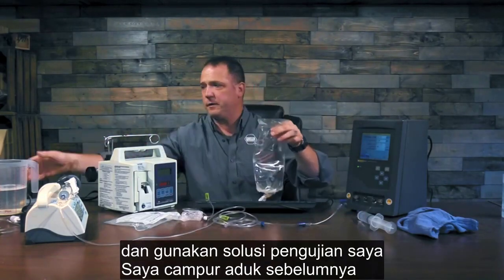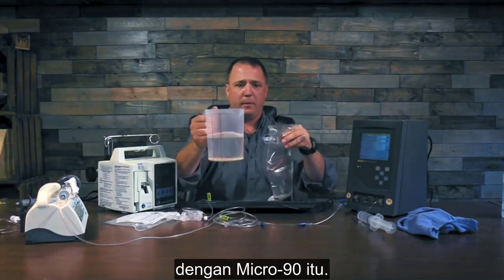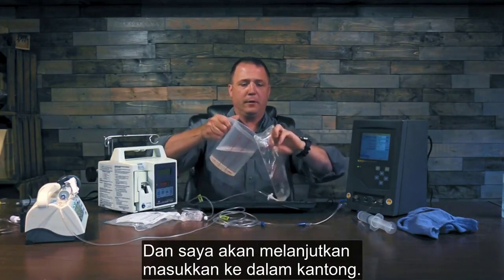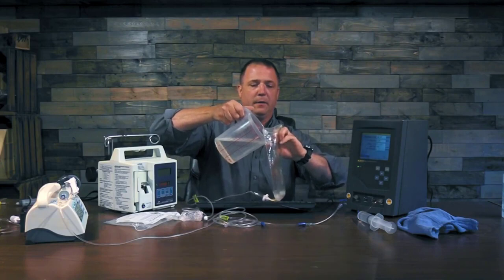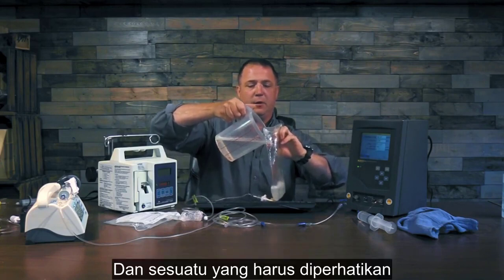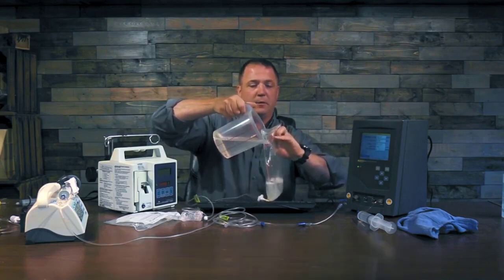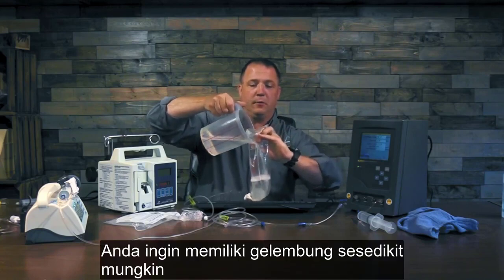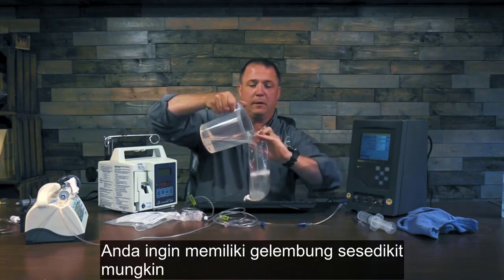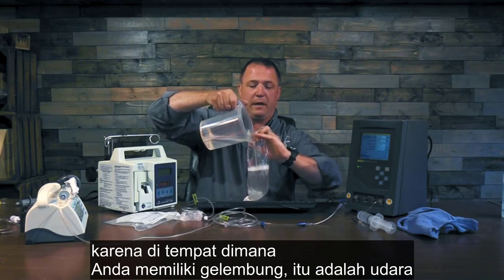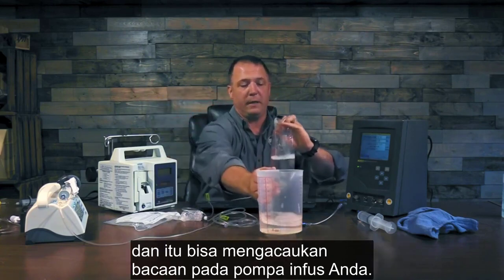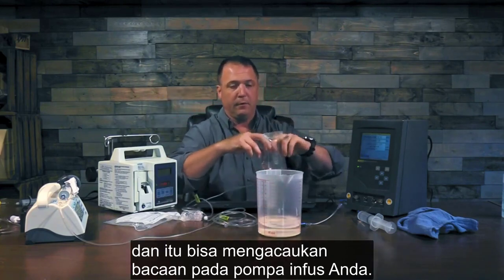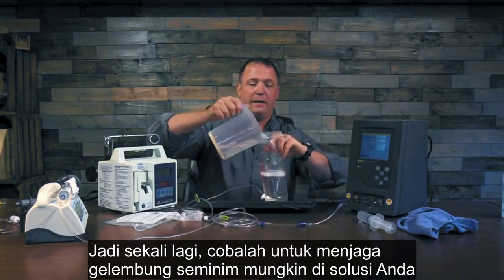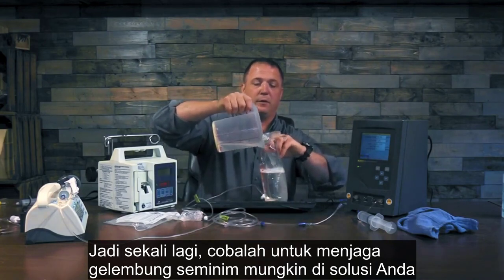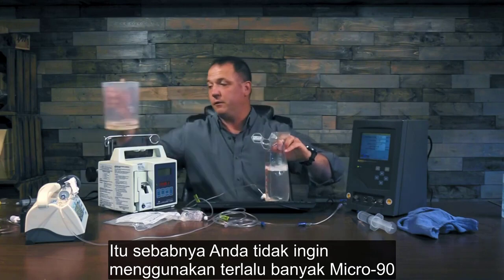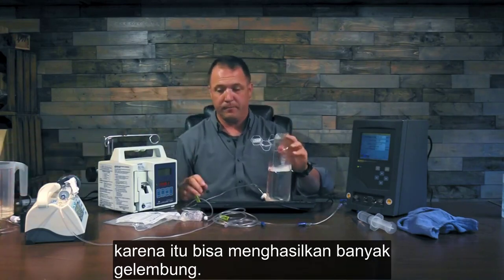Now I'm going to go ahead and use my test solution I mixed up earlier with that Micro 90, and I'm going to go ahead and put it into the bag. And something I should note is you might see bubbles in there. You want to keep as little of the bubbles as possible, because any place that you have a bubble is air, and it can throw off your readings on your infusion pump. So again, try to keep the bubbles out of your solution if you can. That's why you don't want to use too much Micro 90, it can bubble on you.